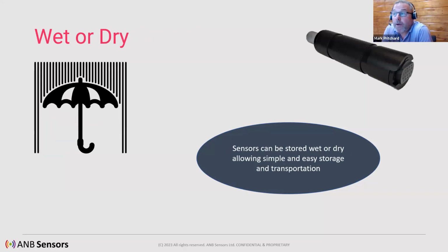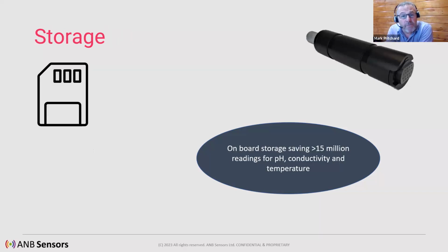It can be stored wet or dry, so you've got no tricky storage requirements—very simple to store and transport. The units themselves have onboard storage, so they become a data logger, storing over 15 million readings for each parameter we're looking at here: pH, temperature, conductivity, and salinity, all stored onto the integral memory.